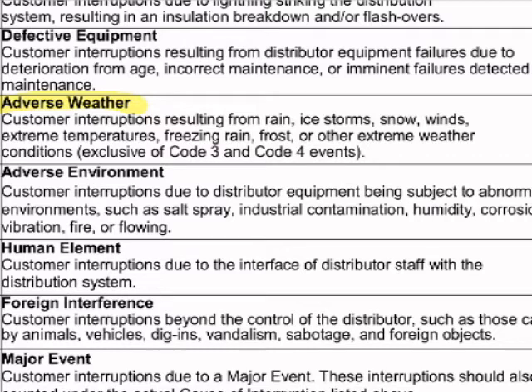You can get heavy frosts if you have an excess of pollution or salt buildup from winter. You can get an excess of that built up, and you can get a flashover over the surface, where the surface of your insulating material stops insulating. And if that happens as a result of a heavy frost, that would be categorized as adverse weather. Again, all of these things are going to result in a fault, all of these things definitely resulting in an outage.